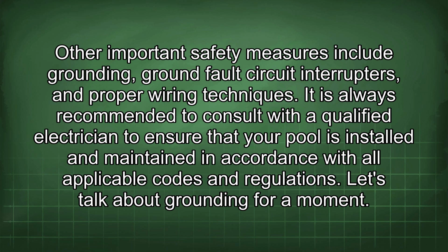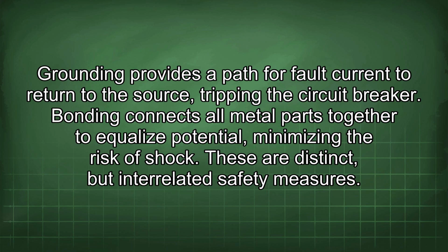Let's talk about grounding for a moment. Grounding provides a path for fault current to return to the source, tripping the circuit breaker. Bonding connects all metal parts together to equalize potential, minimizing the risk of shock. These are distinct but interrelated safety measures.